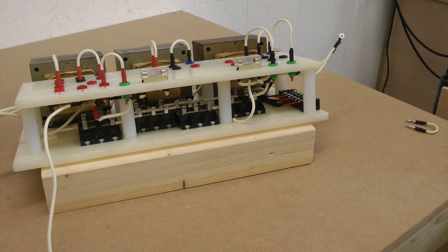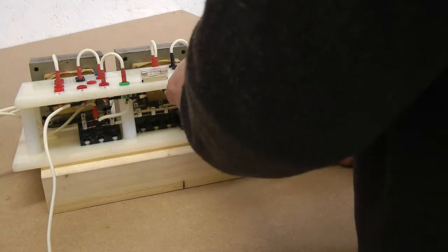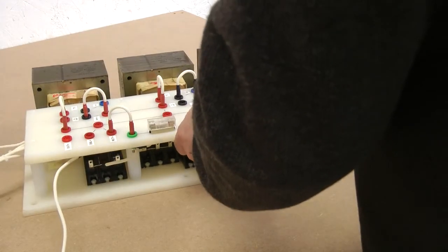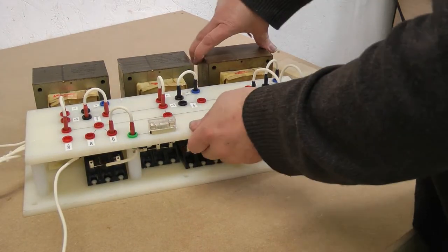Layout is careful, taking into account the type of voltages and currents involved, making sure that circuits are protected with fuses and with the adequate type of wiring that you need for this kind of high voltage supply. But otherwise, it's actually very straightforward. It's just a set of transformers with some rectifiers and a patch board wired up in a way which makes it possible to configure it in all types of different configurations.